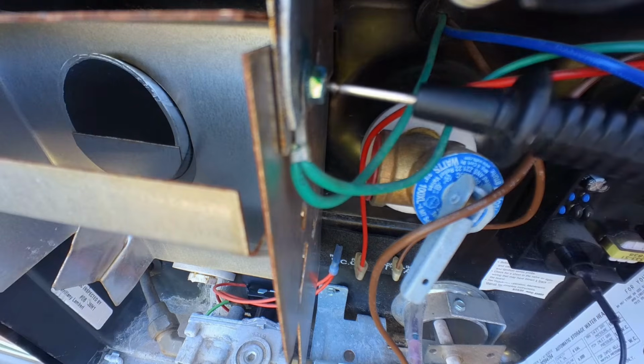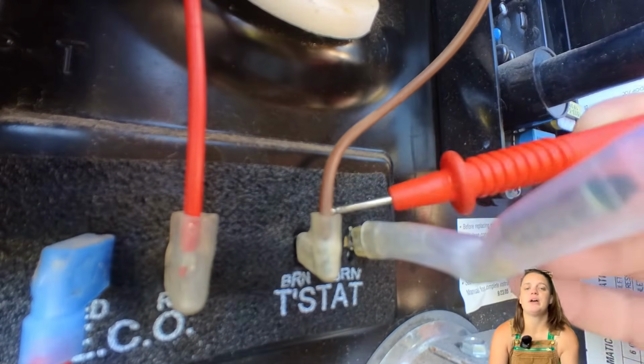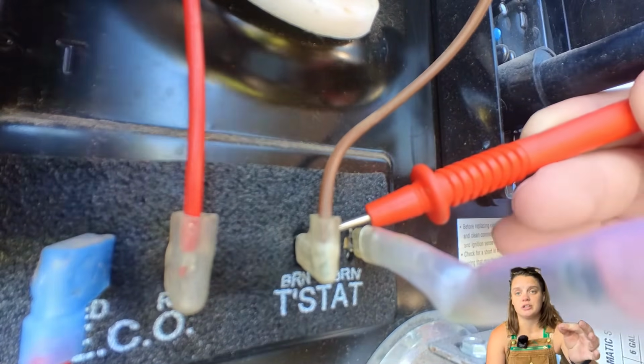I'll talk in just a minute about what the T-stat is, what it does, and how to test it. But first we're going to see if the power is even making it to the T-stat. This is where we test for DC volts. We take one probe and touch it to that screw, and take the other probe and touch it to the terminal coming out of the T-stat. You may need to pull back on the connector on that terminal to expose enough metal to get your probe in.